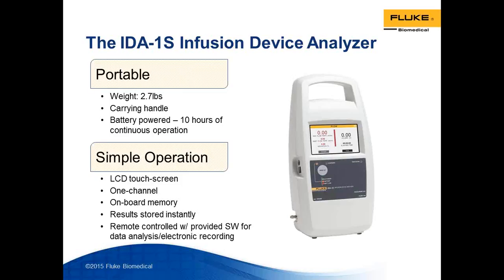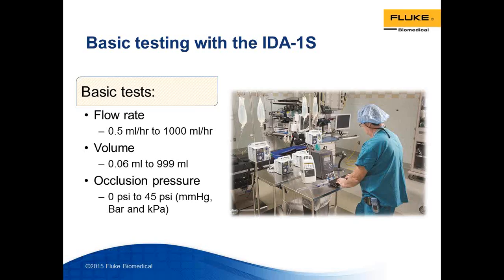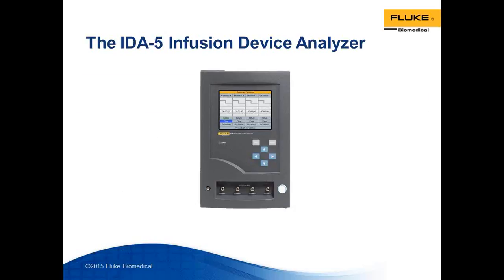So basically a very, very simple analyzer, compatible with any brand, any type of infusion pump. The flow rate is up to 1,000 milliliters per hour. The volume is about, say, 999 ml. The infusion pressure is 0 to 45 psi, and it's available in various formats, including millimeters of mercury, kilopascal, bar, etc. So it does all the basic tests that are required of a simple infusion test analyzer.